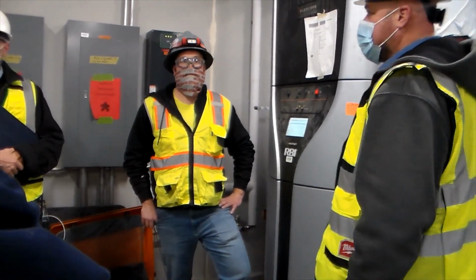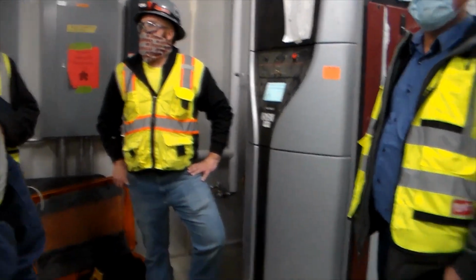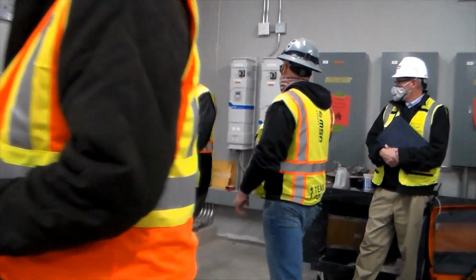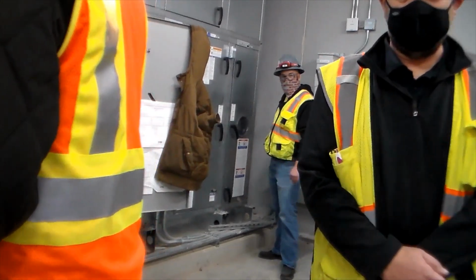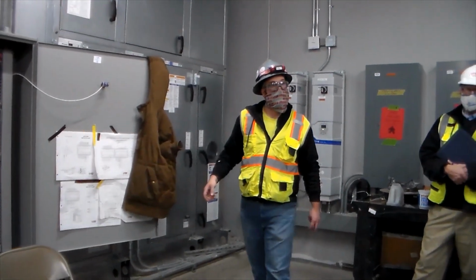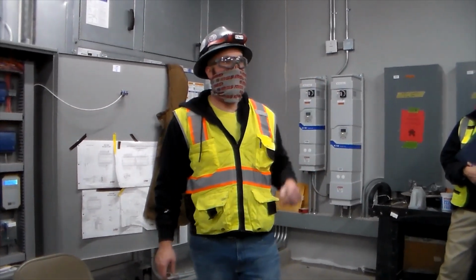Alrighty. Everybody okay? Okay, I guess we'll go to the air handler then. This air handler feeds all the classrooms throughout the building. You will see you have your 2 exhaust direct drive fans back here. They're exhausting right out through the damper. We built it to exhaust rather than intake at ground level because of snow that comes off that roof and piles there.